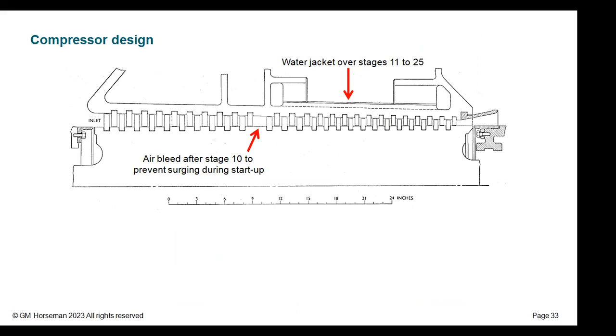Another thing that was done, as labeled on there, was a water jacket put over stages 11 to 25 - that's the outlet end of the compressor. The whole idea was to try and achieve isothermal compression, where the blades themselves act as heat sinks, like fins conducting heat to the water jacket to remove heat. Also, the water jacket would chill the cylinder and cause the running clearances to tighten slightly.